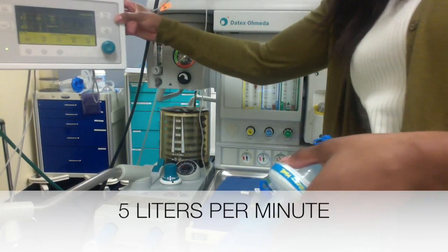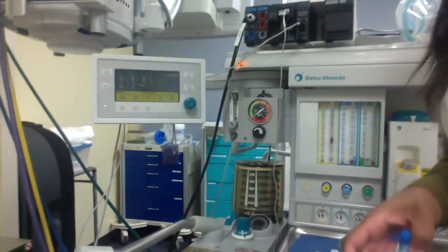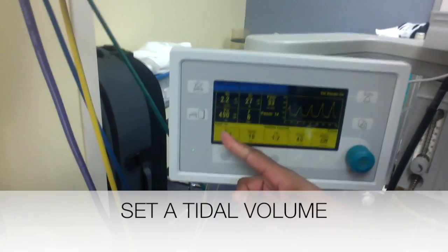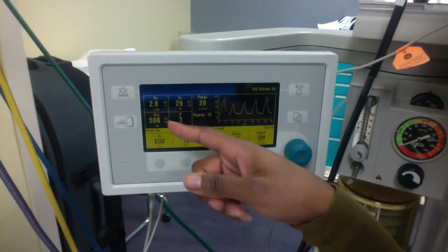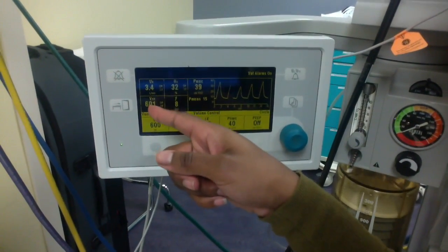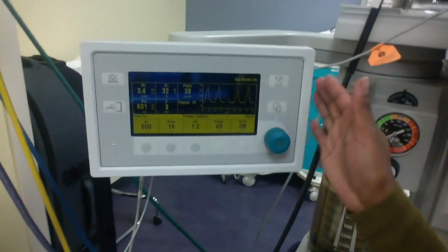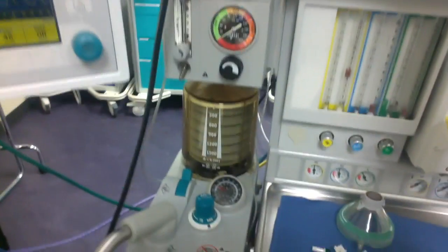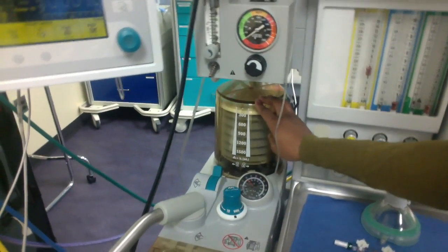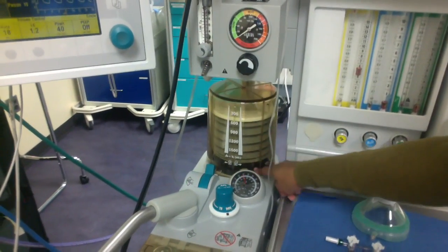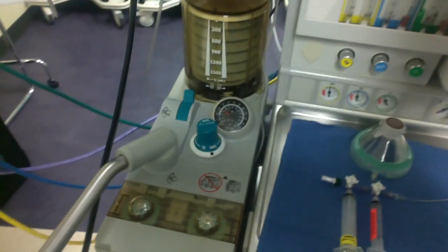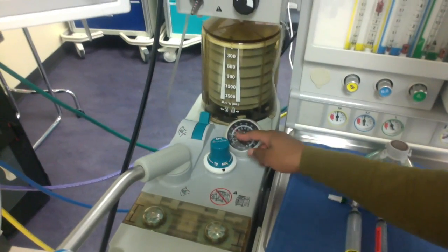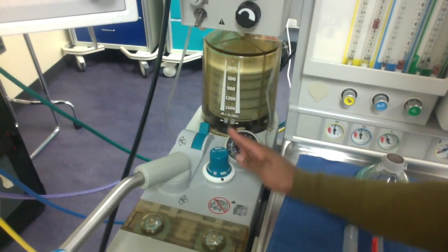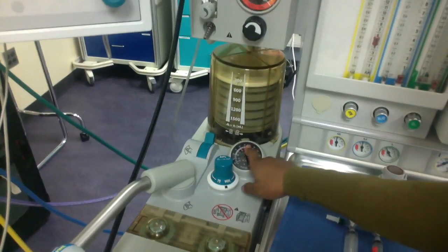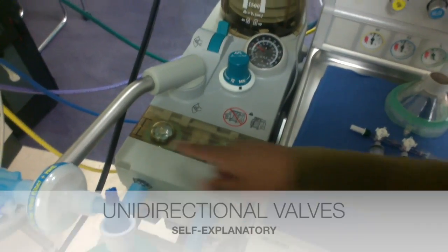So what I'm checking for here is that the tidal volume that I set, I want my machine to be delivering that. So it takes a few cycles to work up to it. Oh, there you go. So now I'm at 600. The machine is delivering what I told it to. So I will come here, and this is all part of the ventilator check. I'm looking at my bellows are rising and falling appropriately, that my pressure gauge is coming back down pretty close to below 10 or closer to 0, and not stacking breaths with each one, so going above 40 centimeters of water. I'm also looking at my unidirectional valves here.